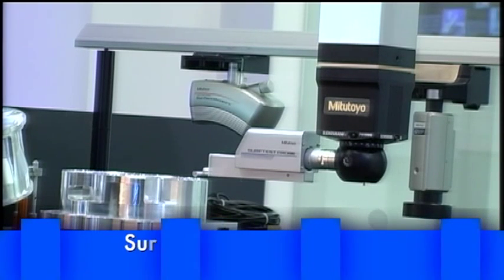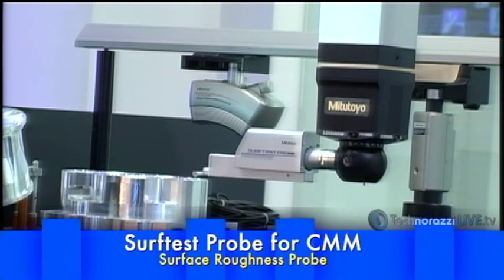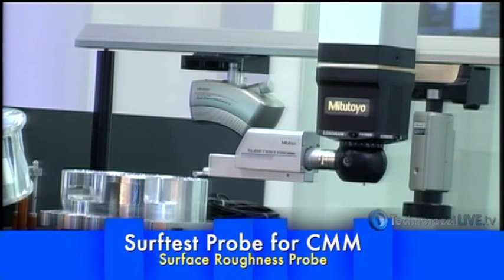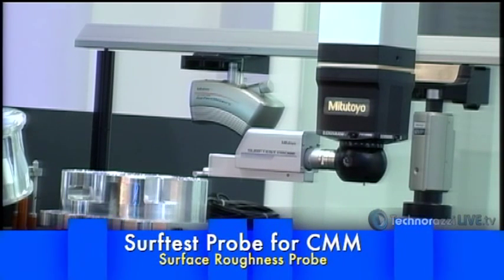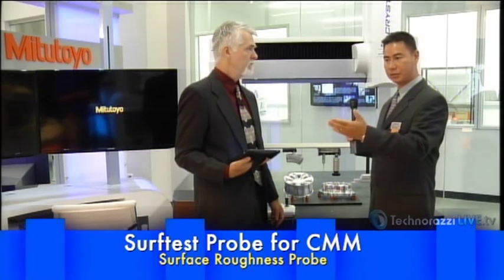Okay, now one thing I'm interested in is, since this is on a CMM, are you able then to correlate that surface roughness measurement with a particular location on a part? Say maybe you've gone around the part, you've scanned it, or you've touch probed it, or whatever. Now you go back in, you pick up your Surftest, you come back in, you make a measurement. So now on the results, you're able to correlate that surface roughness measurement with a specific spot on the part? Correct. You're able to go back to the exact spot and look at the surface analysis of that area through the two softwares that we combine, MCOSMOS and FORMTRACEPAK.